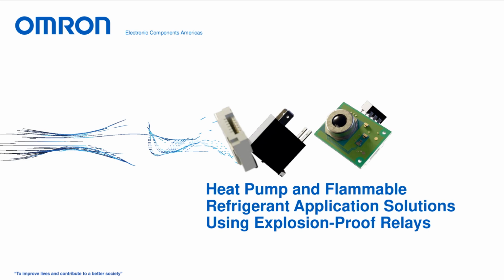So that's also a good question. When the current exceeds 16 amps, the potential for sparking or arcing increases. So that's in accordance with IEC, that's the level in which we start to have that concern. We won't see true problems until maybe after 20 amps, but for that factor of safety, we want to give a number to be the threshold to cut off. So we have that full isolation from the semi-flammable gases. It's really developed by the IEC as that level of dangerous arcing potential. Oh, okay, that makes sense.